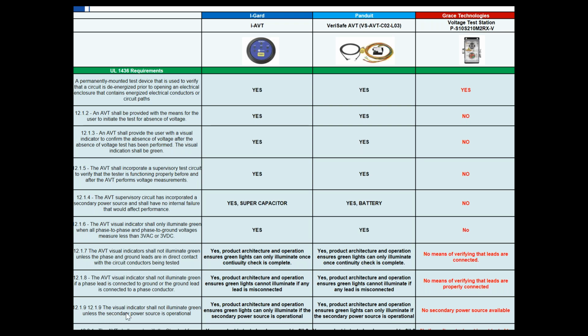12.1.9, so good, you have to mention it twice. The visual indicator shall not illuminate green unless the secondary power source is operational. Yes for the i-Gard i-AVT. Yes for the Panduit VeriSafe. No, the Grace does not comply. 12.2.1, the AVT shall comply with the standard for functional safety 61508 to achieve SIL3 rating. The i-Gard i-AVT, yes, the product does comply with SIL3. Panduit VeriSafe, yes, the product does comply with SIL3. The Grace technology does not comply.